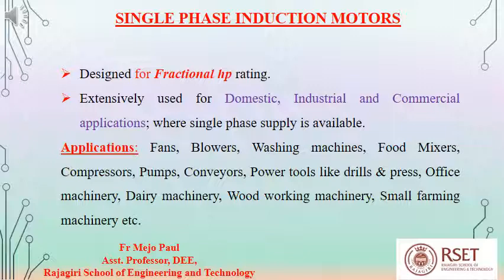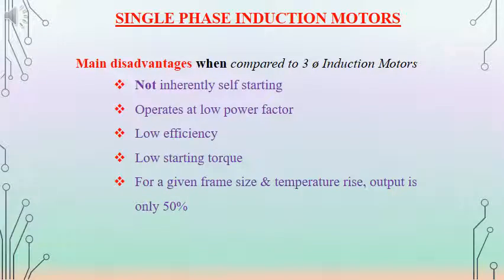Other applications include office machinery, dairy machinery, woodworking machinery, and small farming machinery. The power rating is normally less than 1 hp. Even with so many applications, single phase induction motors have many disadvantages compared to three phase induction motors. Three phase induction motors are inherently self-starting, but single phase induction motors are not. The operating power factor is very low and the efficiency is very less.